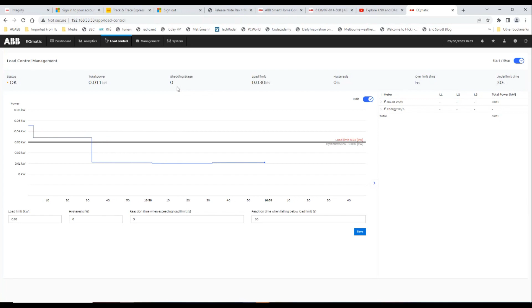So that's our load shedding and how it will work. That load shedding stage can be sent out to some relays, and those relays can decide to turn off a couple of channels. You could also feed that to some logic, and use that logic to turn off some lighting, reduce temperature set points, or any of that sort of stuff to do load shedding if you had to. It's quite useful and quite powerful.